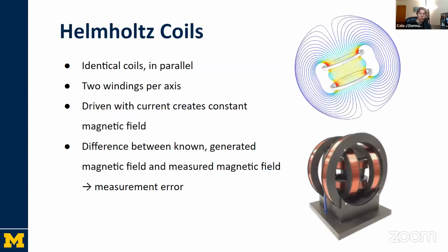Now, what is a Helmholtz coil? Helmholtz coils are identical coils that, when put in parallel and driven with current, create a known constant magnetic field between them. The difference between this known generated magnetic field versus the magnetic field that a sensor in the middle of them would be measuring is the measurement error.